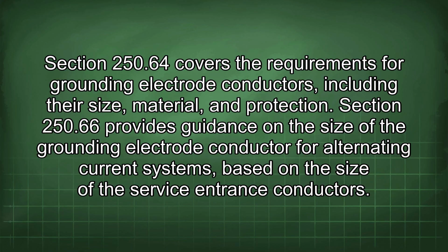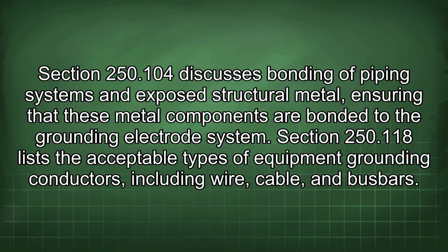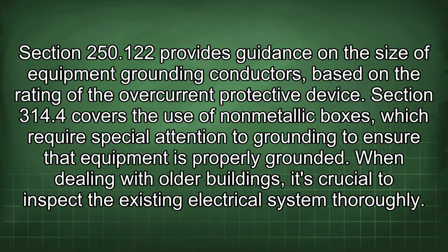Section 250.66 provides guidance on the size of the grounding electrode conductor for alternating current systems, based on the size of the service entrance conductors. Section 250.104 discusses bonding of piping systems and exposed structural metal, ensuring that these metal components are bonded to the grounding electrode system. Section 250.118 lists the acceptable types of equipment grounding conductors, including wire, cable, and busbars. Section 250.122 provides guidance on the size of equipment grounding conductors based on the rating of the overcurrent protective device.